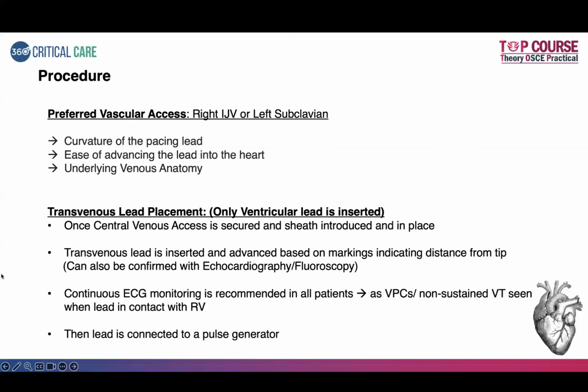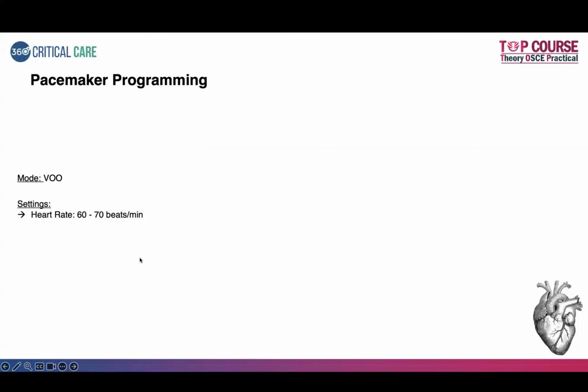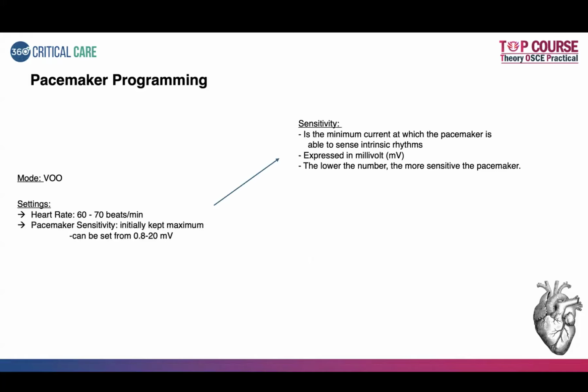So the routine settings that are kept: the heart rate is usually kept between 60 to 70 beats per minute. The pacemaker sensitivity. So what is it? It is the minimum current at which the pacemaker is able to sense intrinsic rhythms. It is expressed in millivolts, and its significance is the lower the number, the more sensitive the pacemaker. It is usually kept between 0.8 to 20. Initially you keep it on the higher side and then you slowly come down. Usually 0.8 should be the lowest number that should be kept, because at that level, if you are able to sense the rhythms, then that is a good sign.